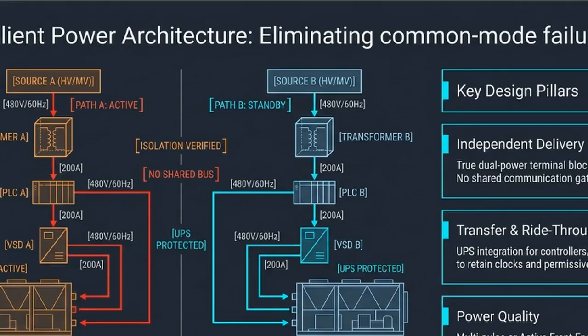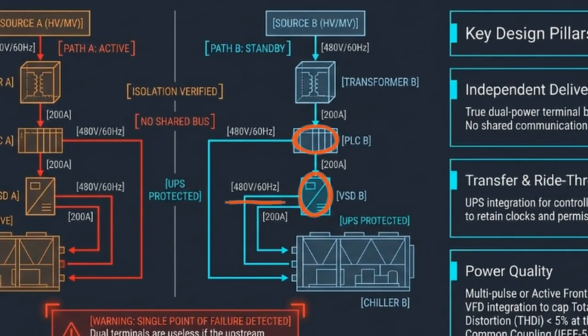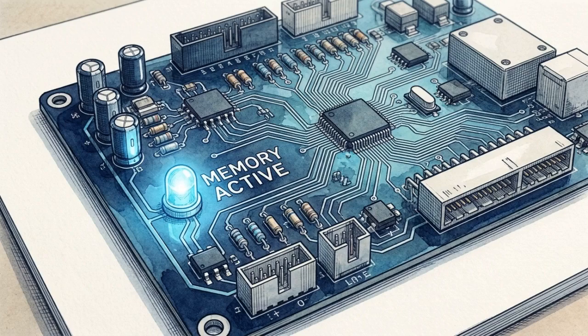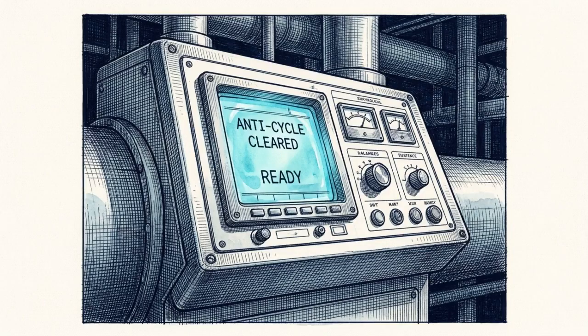To prevent this, dedicated protection sits directly within the power path. Uninterruptible power supplies, or UPS modules, feed the localized programmable logic controllers and variable speed drives. Retaining UPS power for these controllers preserves their active memory and anti-cycle permissives. The chiller remembers its operating state, preventing it from triggering catastrophic hard-coded lockout delays during the transition.